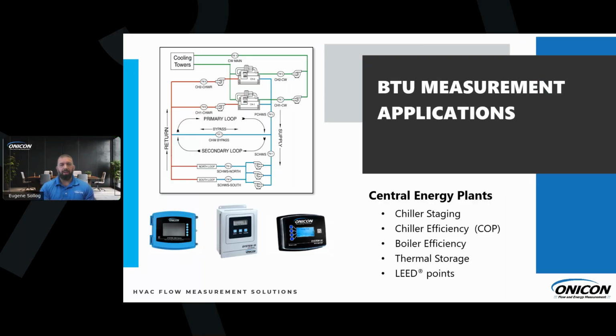Also, with this meter, it can be used in conjunction with one of our BTU meters. The three on the bottom left you're seeing are the System 1000, the System 10, and the System 20. This inline mag meter can be used in conjunction with any one of those flow meters. Just depends on what outputs you need from those flow meters.